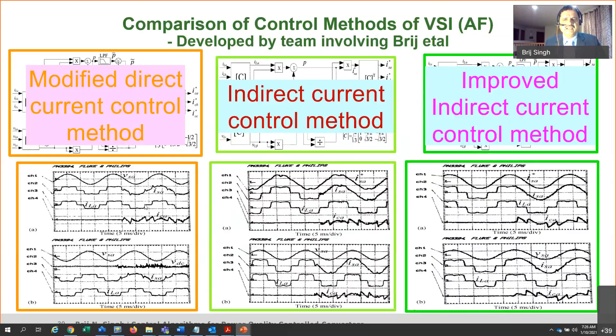So your load THD would be 29%, that's the TDD. With one method you get 10.2 — you need to go below 5. With the other method, because of distortion, you have 7.1. And with the last method, which is a much improved method, you get 3.2.